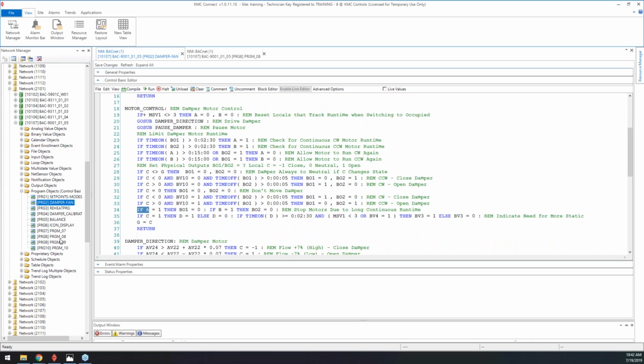Don't change our code; write in a custom program and write over top, or command the variable or output at a higher priority. That way our code can run underneath yours, and you can see that our code is running, but you can also see your code running.